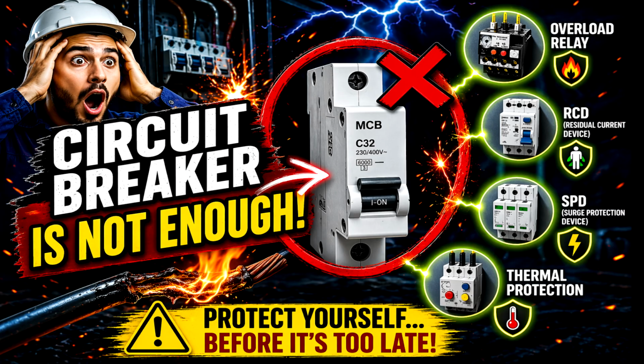Very important for motors. Second type, residual current device, RCD. This is the real lifesaver for humans. How does it work? If there is any leakage current, meaning current leaves its normal path, for example through a human body, in that moment, it trips instantly. It protects against electric shock.